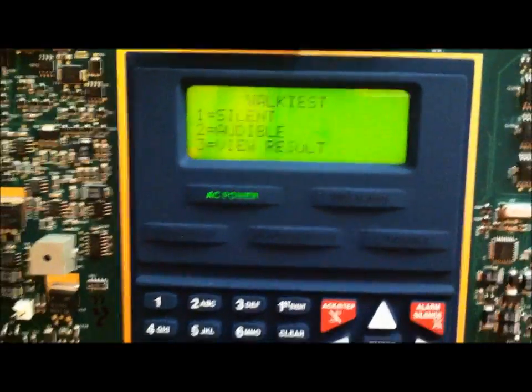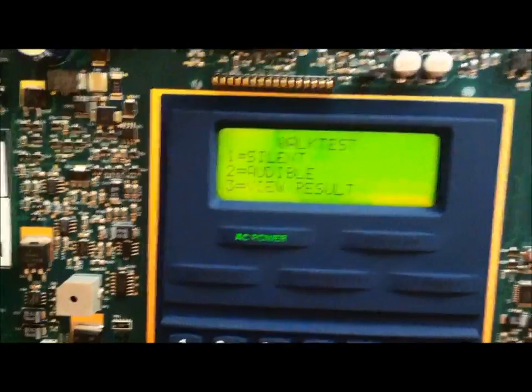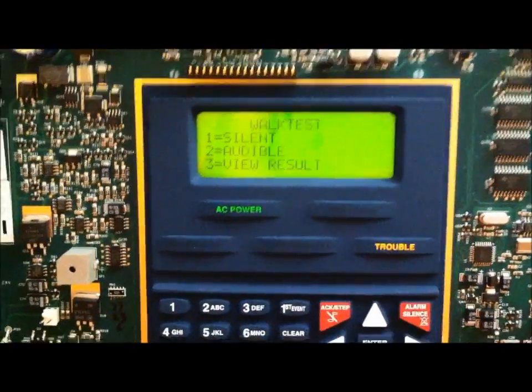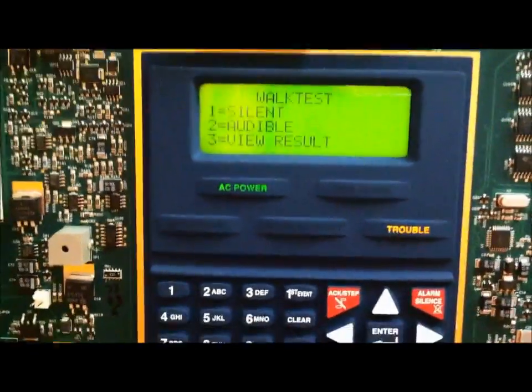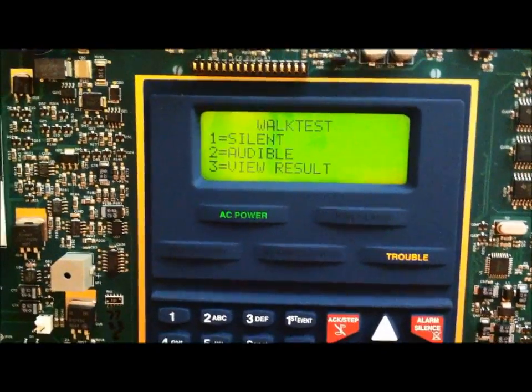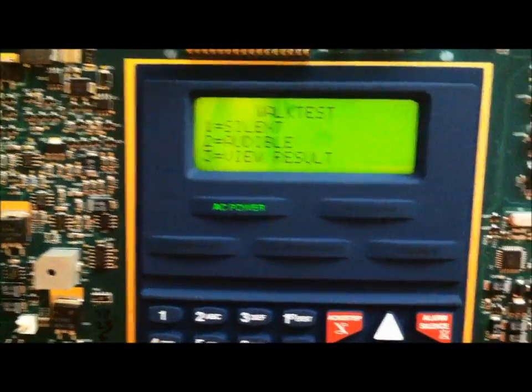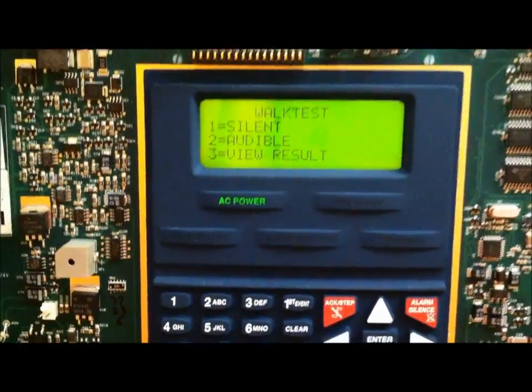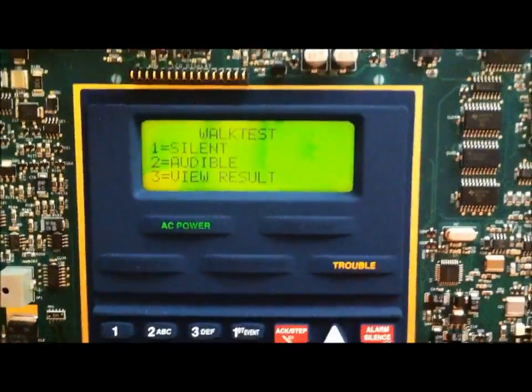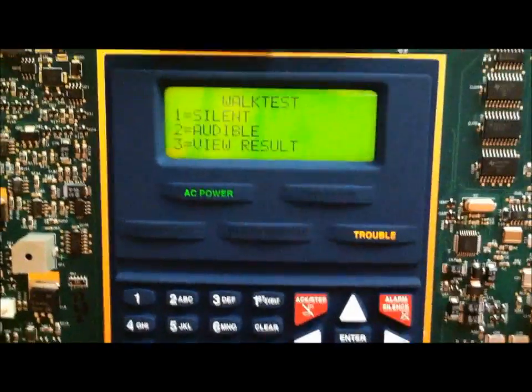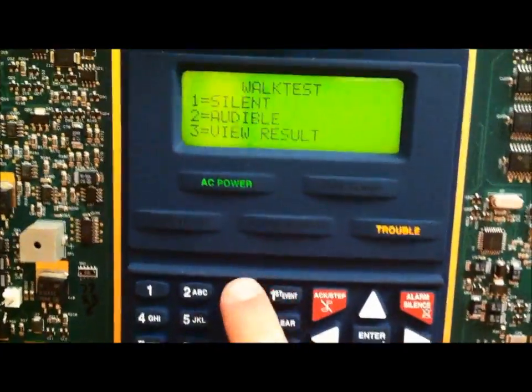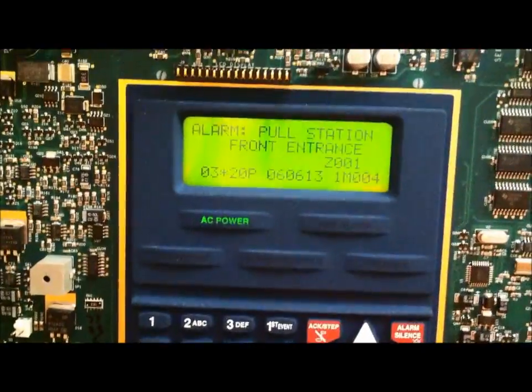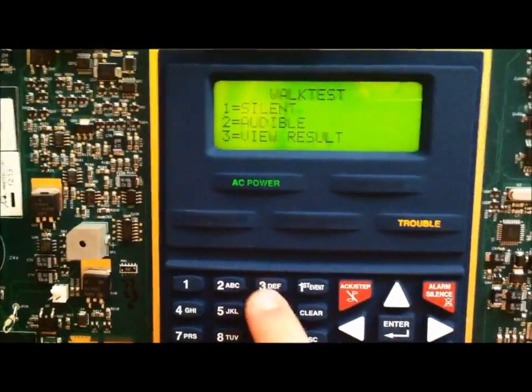And some systems will sound them based off of the device's address. So, if I were to activate, like, pull station number 4, with a point of 4, it will cause the notification appliances to pulse 4 times. And both of these store the walk test information. So, let me go in and see something here. Now, if you were to press 3...